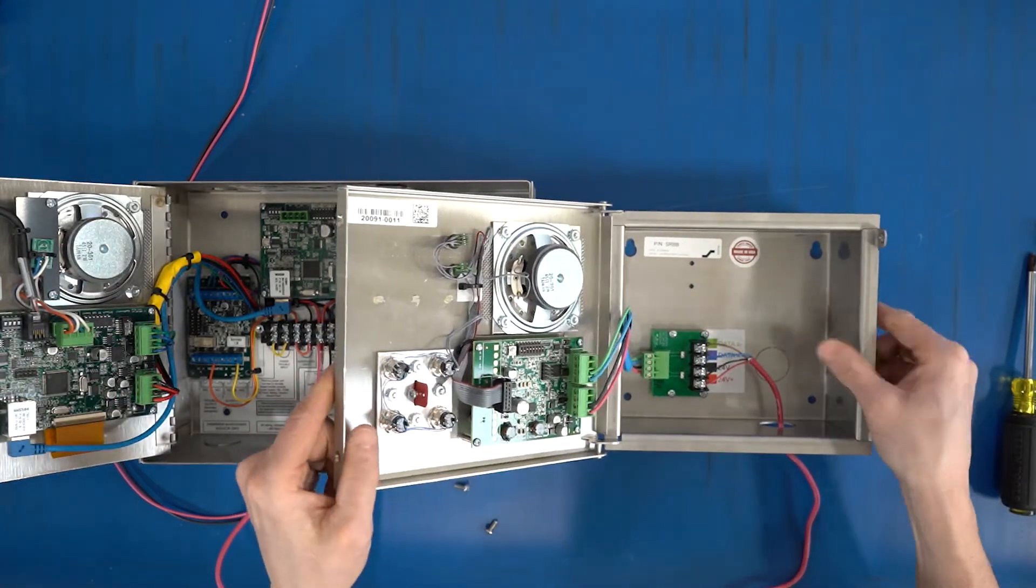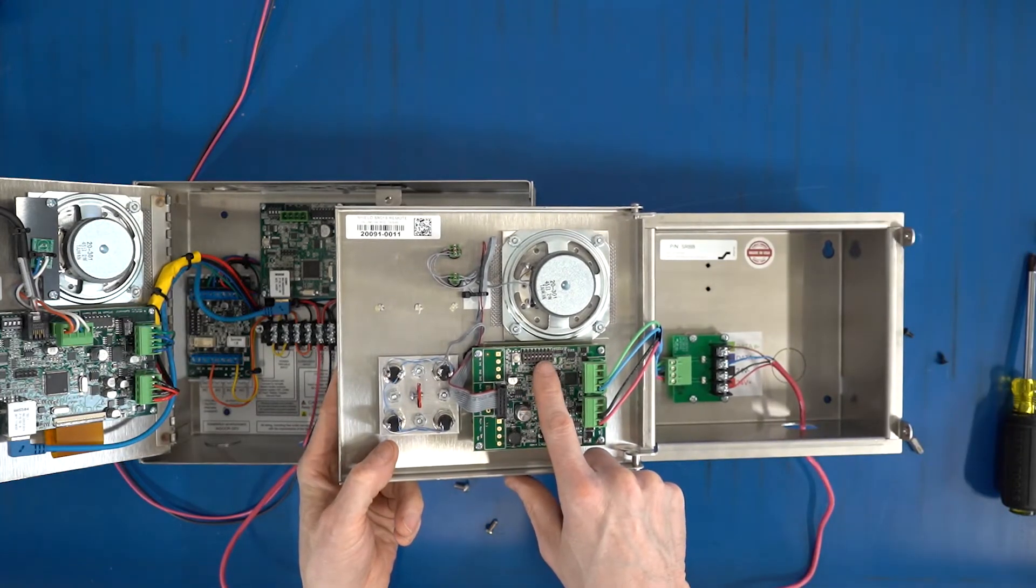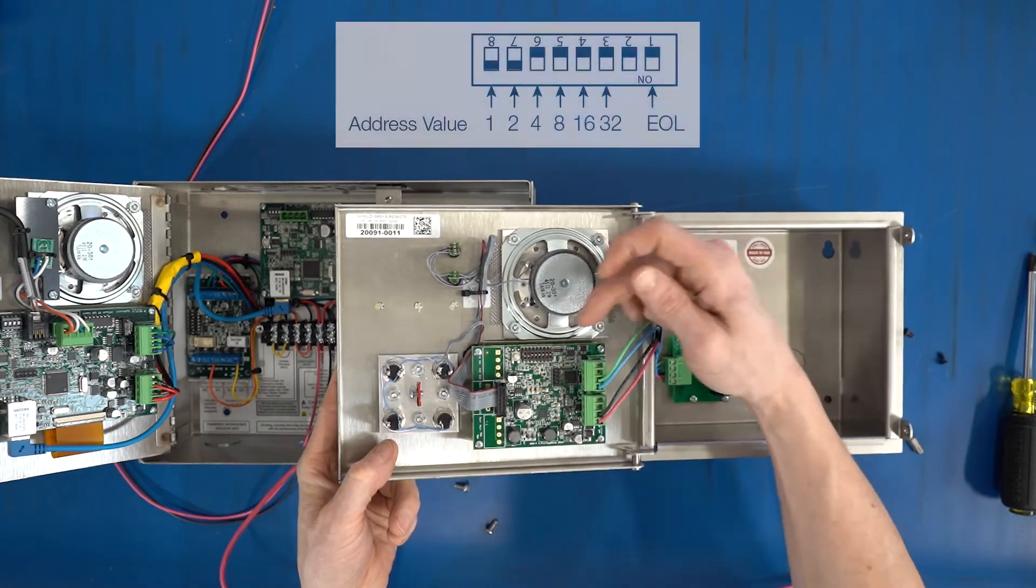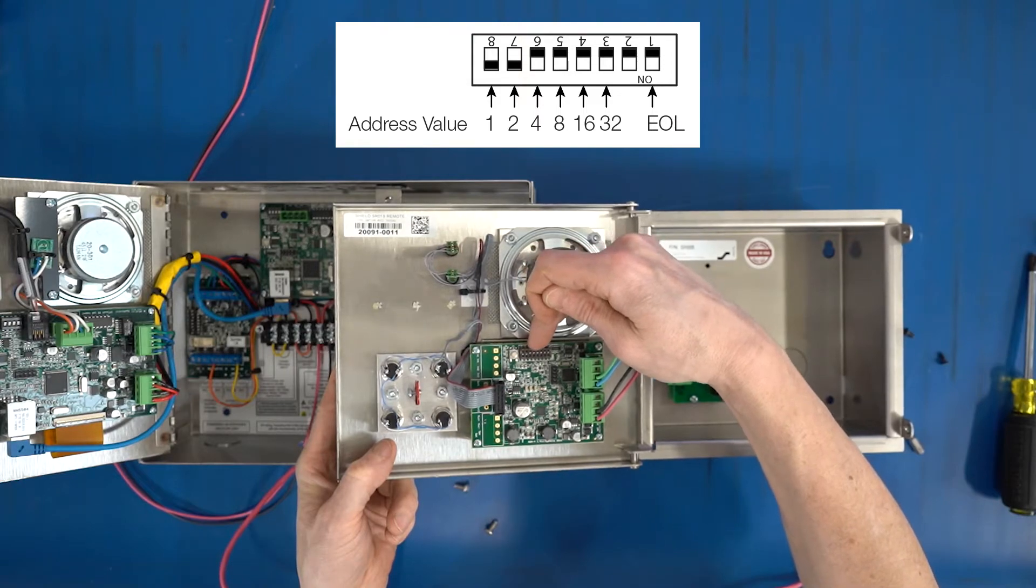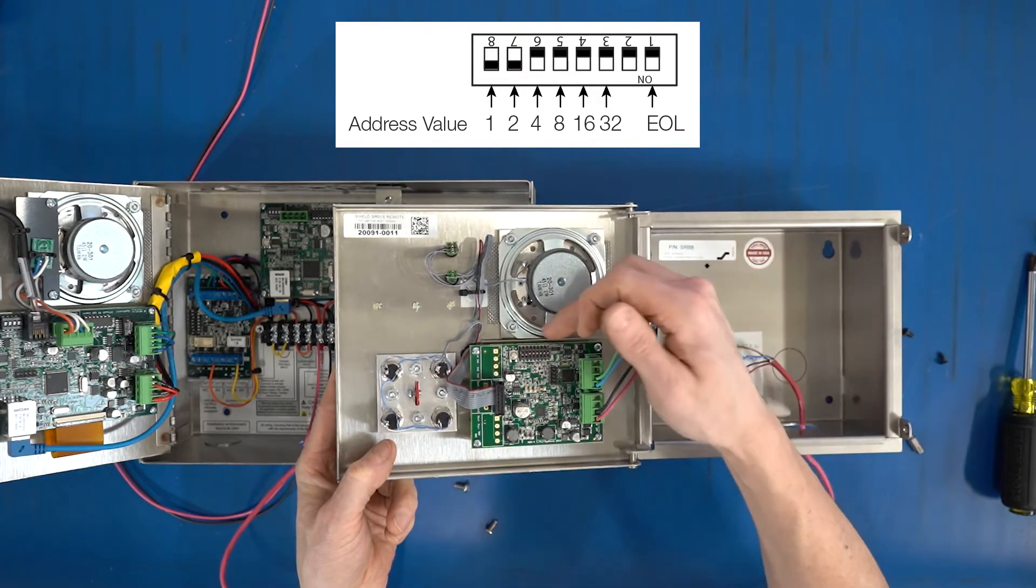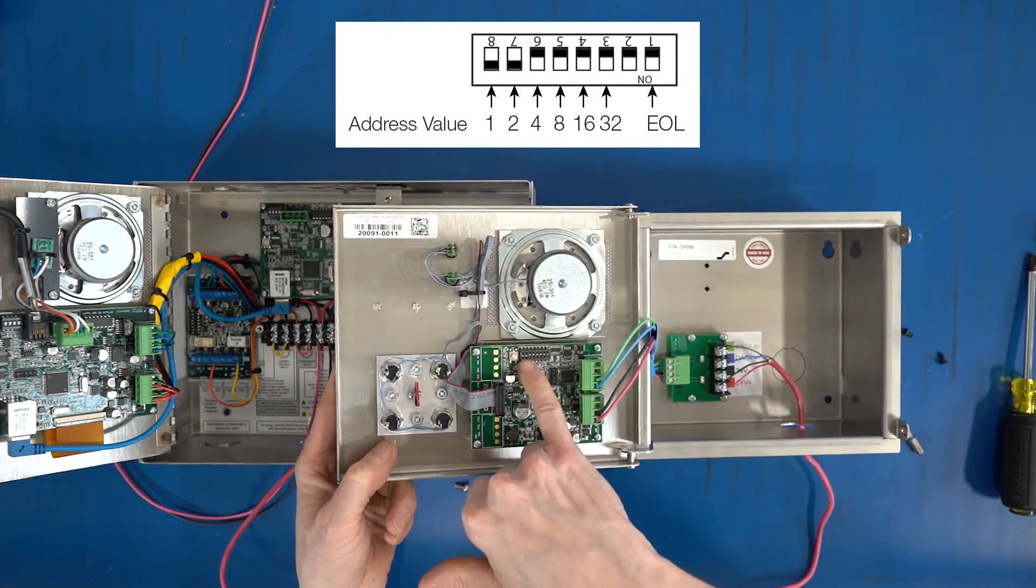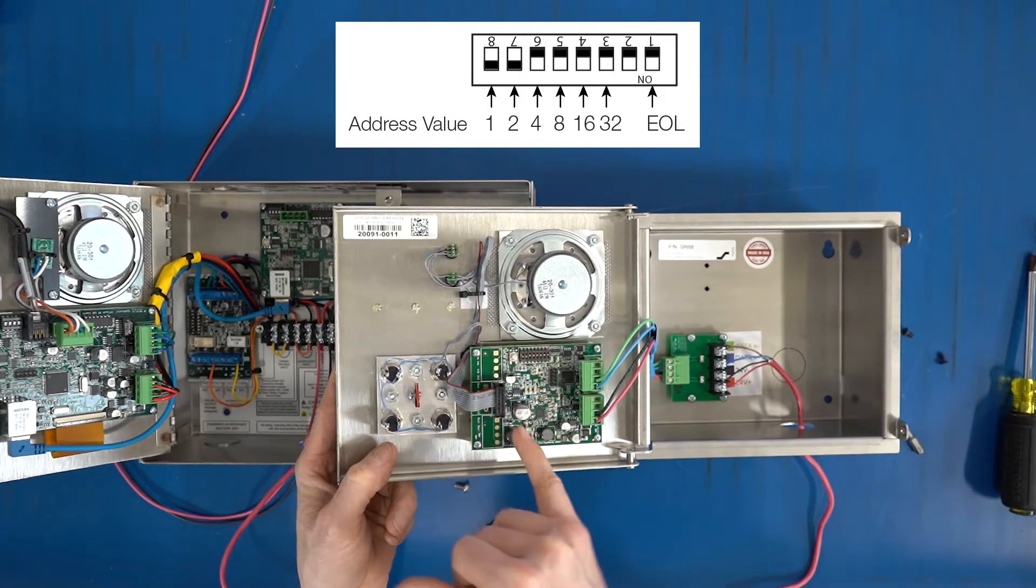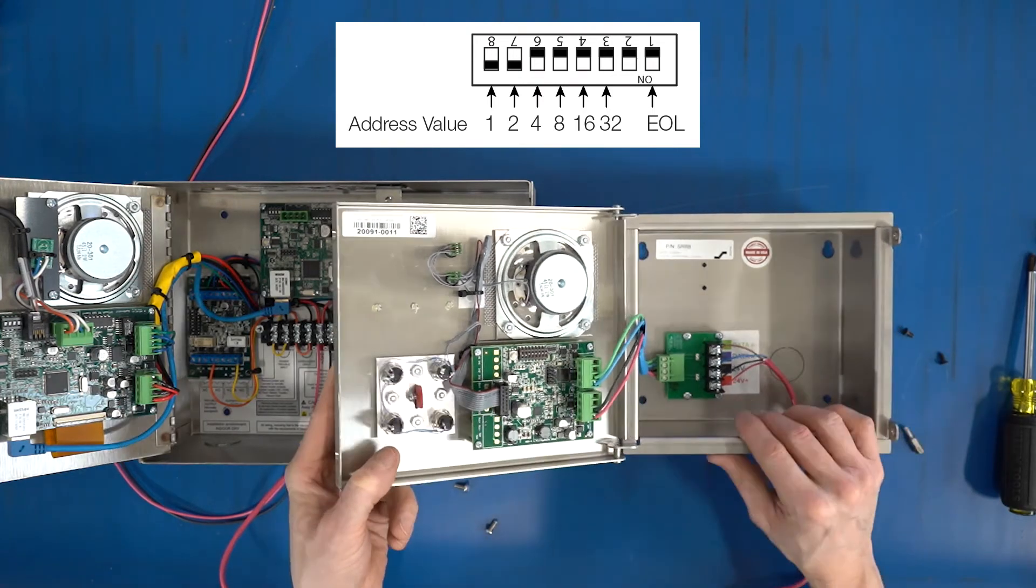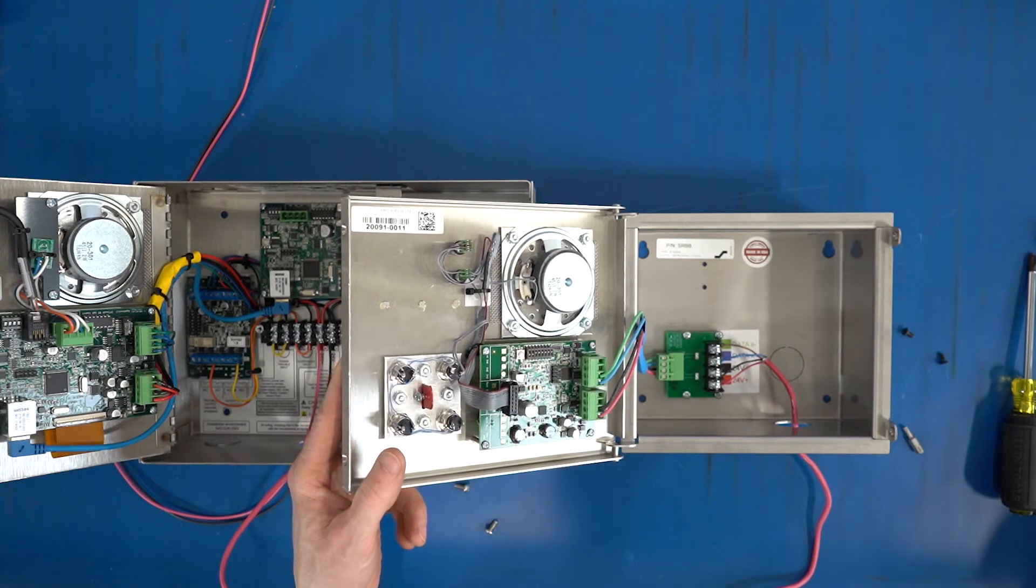The remote has the dip switches on here for addressing. Default address is 3, and this goes in order: 1, 2, 4, 8, 16, 32 addresses, and it's additive, so 1 plus 2 is address 3. On the device itself on the dip switch it actually reads 8, 7, 6, 5, but it's left to right: 1, 2, 4, 8, 16, 32. So I'm going to leave that at default.